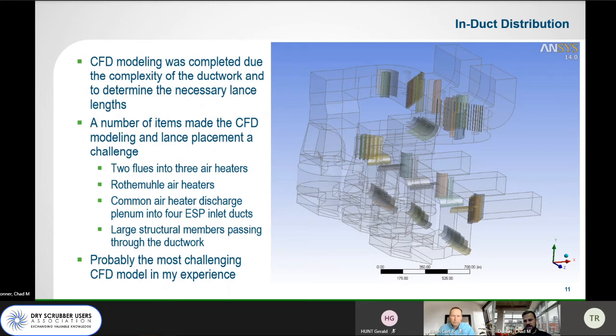So it's kind of tough to tell in this wireframe model, but they had 2 exhaust flues that split into 3 different air heaters. 2 of the outboard air heaters wrapped around the ends, and then the center one dropped out of the bottom of the ductwork. And then all 3 air heaters exited into a common plenum, which then exited into 4 separate ESP inlet flues. So a lot of things happening here with a lot of turning vanes. Probably the most challenging CFD model and distribution challenge that I've had out of any site.